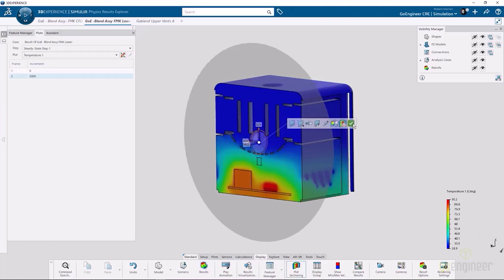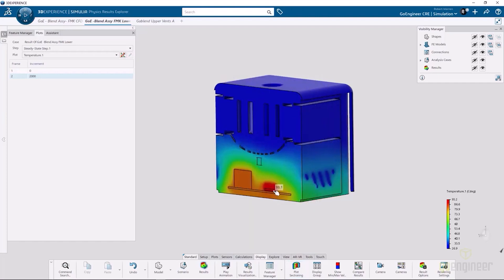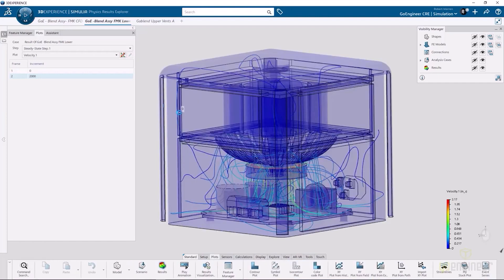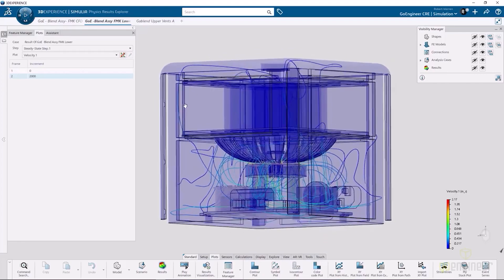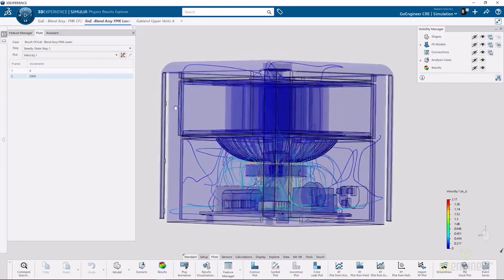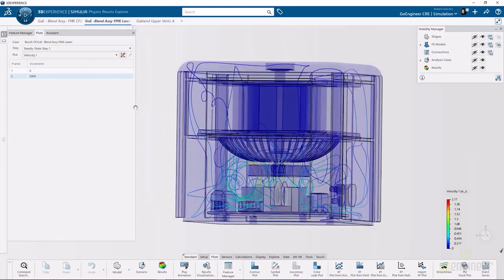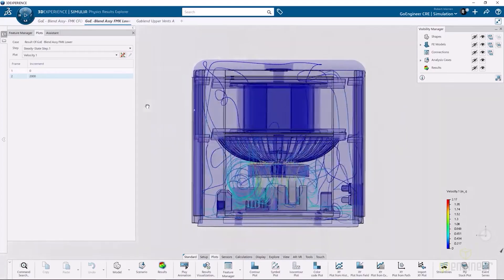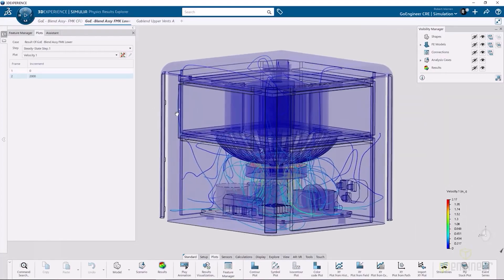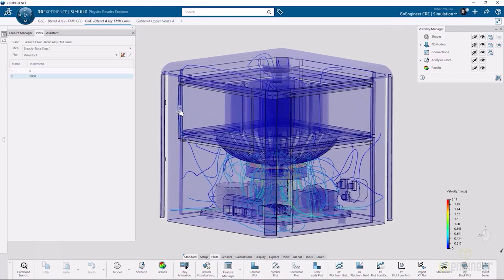We can also look at temperature. This was the main concern we had. I'm doing a cut through of the chip and we can see it's 93.2 degrees Celsius. We're exceeding our temperature. The lower vents are not going to work. We're also seeing the flow trajectories, and the bulk of the air is mainly at the bottom of this study, kind of holding in that heat. We're not cooling that chip enough.